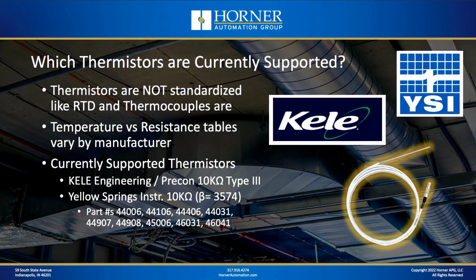Because as I've mentioned a couple times already, thermistors are not standardized like RTDs and thermocouples are, and the resistance versus temperature tables can vary by manufacturer. So at Horner, we support a couple of brands of thermistor manufacturers that have been around for a really long time, starting with Kele Engineering.